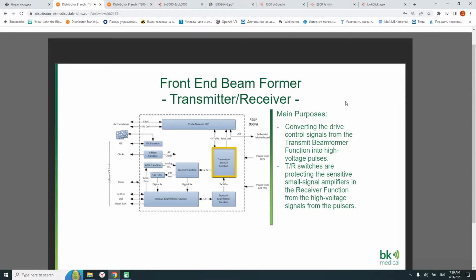The transmit pulsers are responsible for converting the drive control signals from the transmit beamformer function into high-voltage pulses that excite the transducer arrays, thus generating a sound field in the tissue. The transmit-receive switches are responsible for protecting the sensitive small signal amplifiers in the receive function from the high-voltage signals from the pulsers and for removing the load on the element wires during receive.